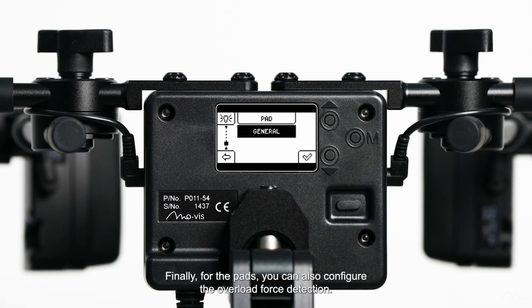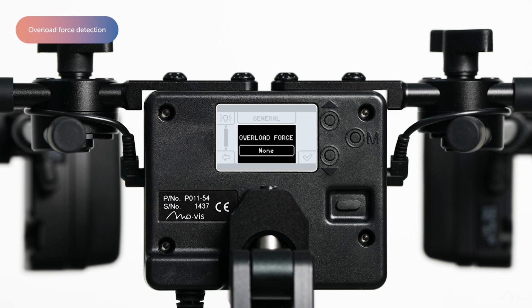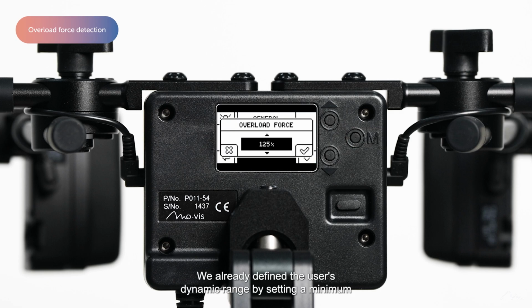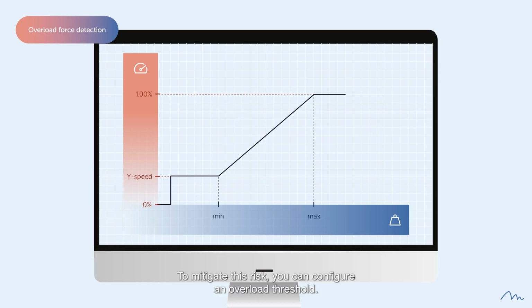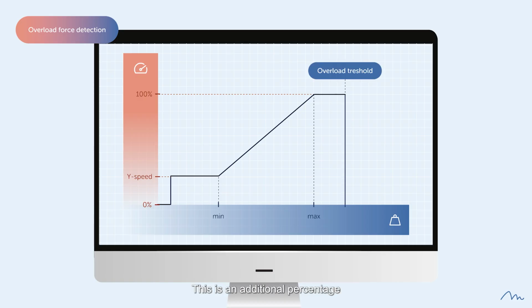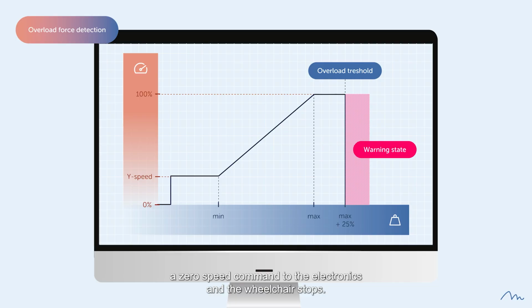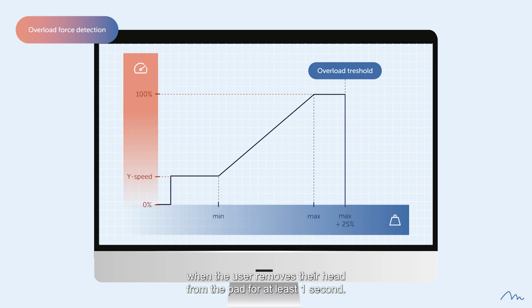Finally, for the pads, you can also configure the overload force detection. We already defined the user's dynamic range by setting a minimum and maximum force. But in case the end user has spastic movements where the muscles contract and they go into an overstretch, the pad may be activated involuntarily, causing the wheelchair to drive unintentionally and possibly hit something. To mitigate this risk, you can configure an overload threshold. This is an additional percentage above the maximum force at which the wheelchair will stop moving. If the user goes into overstretch, the applied force may exceed the overload threshold. In that case, the head control sends a zero-speed command to the electronics and the wheelchair stops. The head control warning state is automatically cleared when the user removes their head from the pad for at least 1 second.